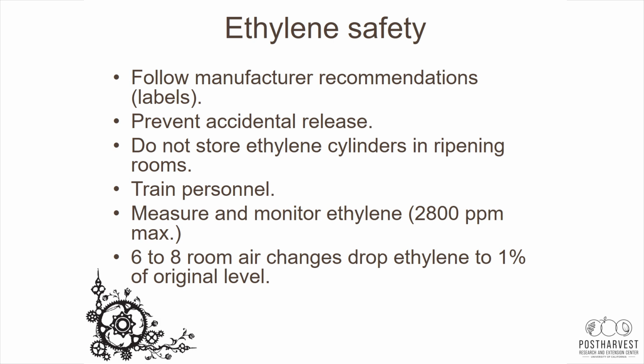Ethylene is explosive at very high concentrations, much higher than the concentrations that you're dealing with in the ethylene rooms. But still, my recommendation is that you need to follow the manufacturer recommendations, especially the labels. In refrigeration and so on, ammonia is much more of a concern, if you ask me. But we also need to be cautious.